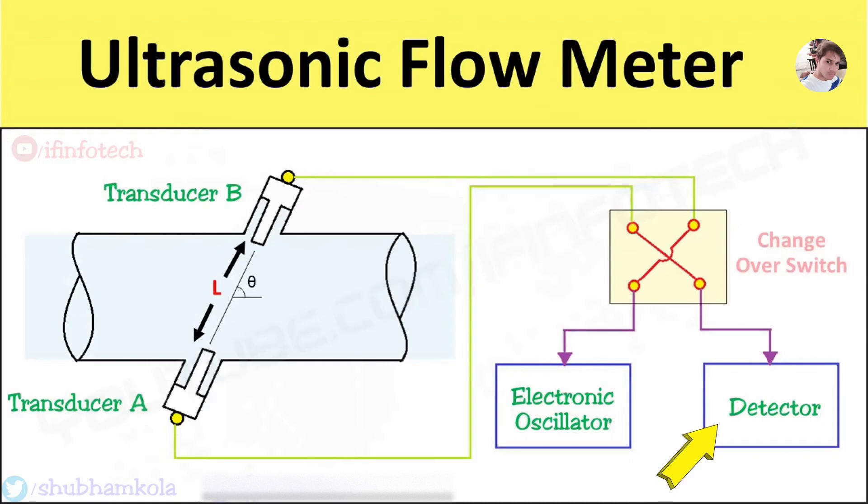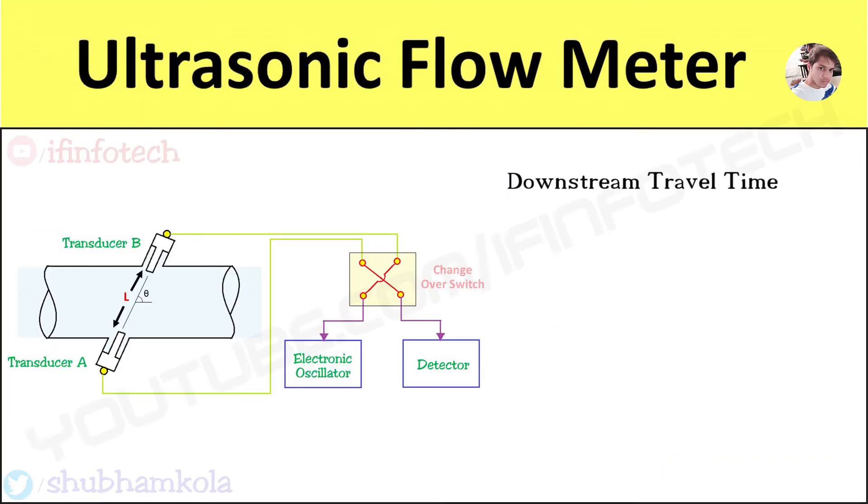Here, downstream travel time is the time for ultrasonic energy to go from transducer A to transducer B, and is given by the expression TAB equals L divided by C plus V cos theta. Here, C is the speed of sound in fluid, L is the acoustic path length in fluid, and theta is the angle of path with respect to pipe axis.